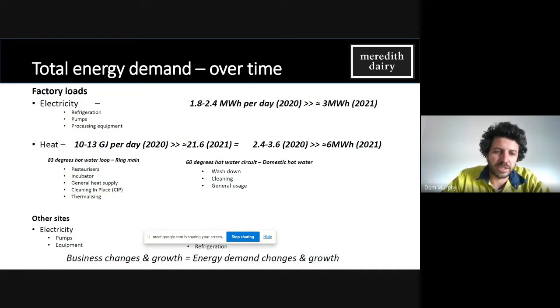One is for a system that we call the ring main, which is for pasteurizing, incubating yogurt, thermalizing, so essentially pasteurizing whey again, and cleaning, and that water is actually retained. So we heat it, draw heat off it, and then reheat it, but the water doesn't change. And then we have another circuit, which is for actually washing things. So that goes down the drain every day and goes out to our settling ponds to be processed. And that is a lower degree circuit, and we call that the domestic hot water circuit.